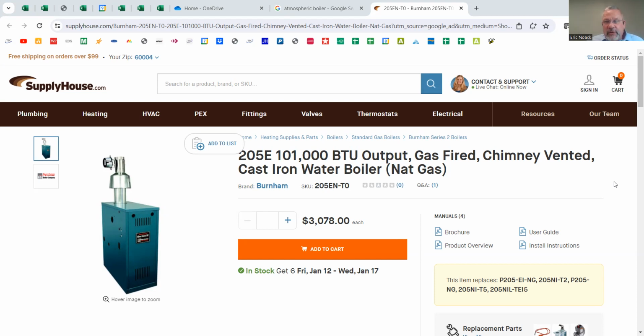So what this really comes down to is, with a forced air system, we have to know the duct capacity to determine if it can handle the air conditioner and or the furnace that we want to put into that home. With boilers, you can oversize and it'll still work. Eventually, though, you'll have problems. But the reality is all that extra doesn't go anywhere. There are simple calculations that can be used, and there's a bunch of different resources online for it. You can calculate the output capacity of the radiators that are existing, and anything beyond that is just wasted. There's no more energy that can come out of those other than what you're calculating from that perspective.